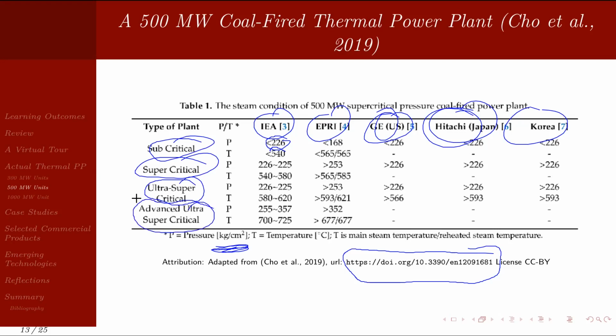There are 4 types. Of course, with advanced ultra supercritical, the pressure is highest, obviously 255 to 357 kg per centimeter square. And look at the temperature — between 700 to 725. Much higher. For ultra supercritical, the temperature range is between 580 to 620.